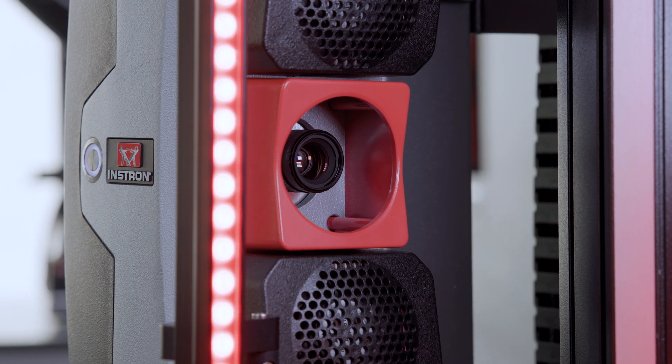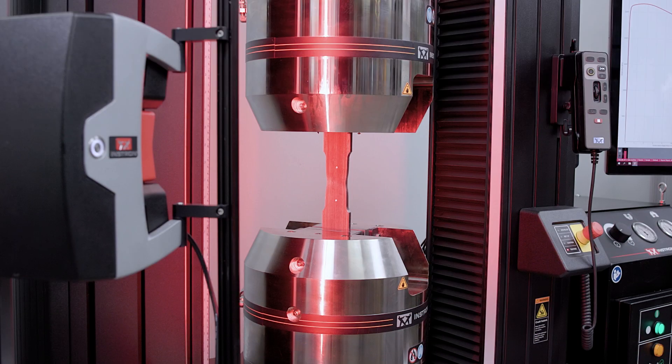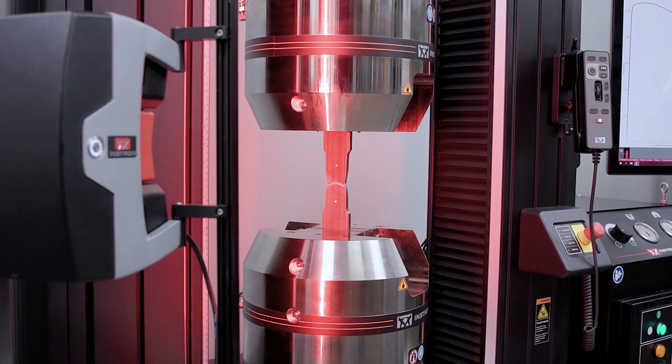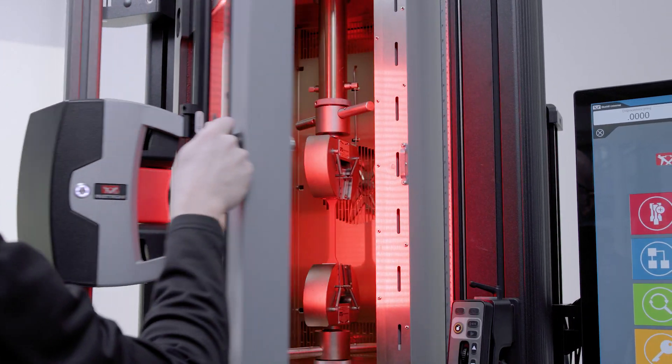The AVE2 provides repeatable measurements down to one micron accuracy and can be used to measure specimen strain from modulus through failure on any material and in any environment without risking damage to the device.